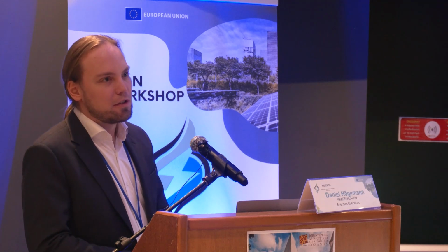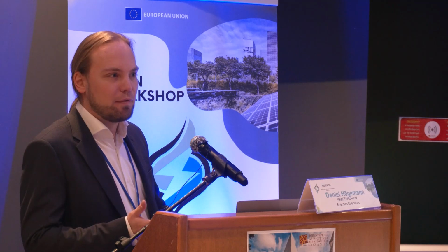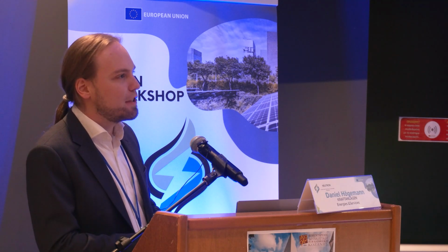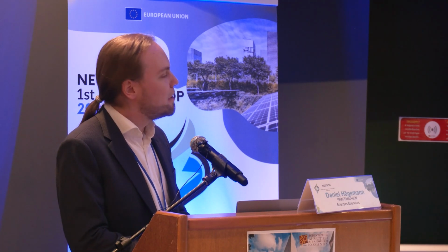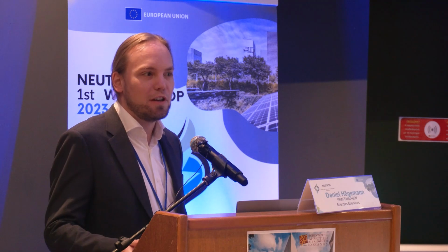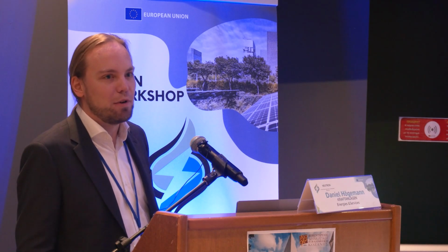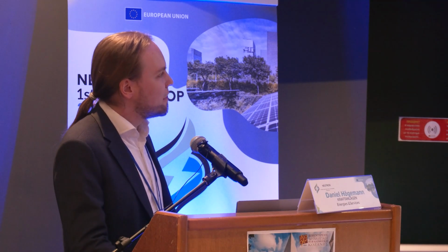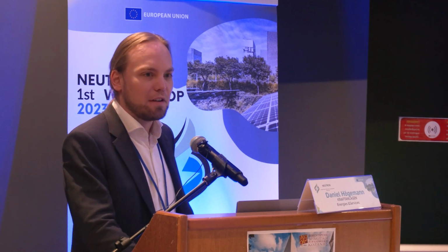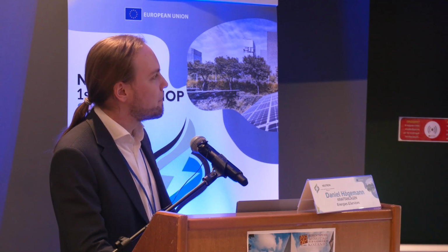What the system also could incorporate would be an optional fuel burner. So for situations when the thermal storage is empty and there is no electricity available, for security of supply reasons, there can be integrated a burner, for example, burning natural gas or biogas, or in the future we can think about hydrogen or ammonia, basically any renewable generated fuel that could be available in the future to secure the supply, even when the storage is not charged by renewable electricity.